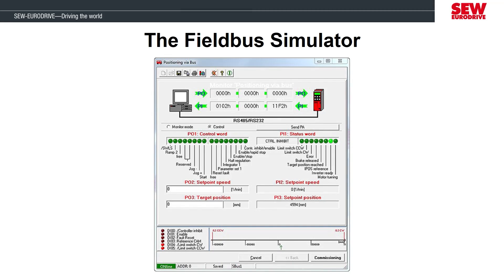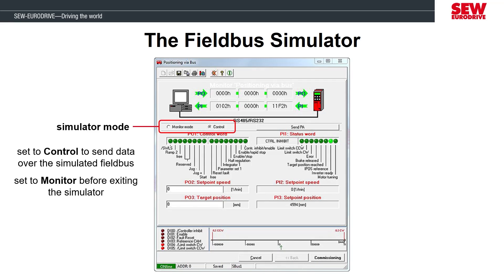This application module is fieldbus based, so it will use a different control method than what we saw in Lab 9. There are two modes of the simulator screen. In monitor mode, we can view the process data going between the upper level device and the Movi Drive, but we won't be able to manually override any of that traffic. To manually control the application using the simulator, we first need to switch to control mode. When in control mode, use caution just like you would in manual mode, because your computer will be taking full control of the Movi Drive. Once done, we have to switch back to monitor mode to allow the upper level device to take back control.